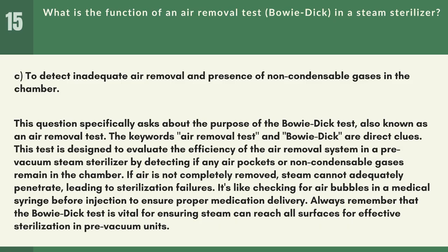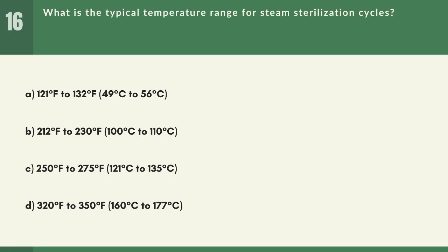If air is not completely removed, steam cannot adequately penetrate, leading to sterilization failures. It's like checking for air bubbles in a medical syringe before injection to ensure proper medication delivery. Always remember that the Bowie-Dick test is vital for ensuring steam can reach all surfaces for effective sterilization in pre-vacuum units.